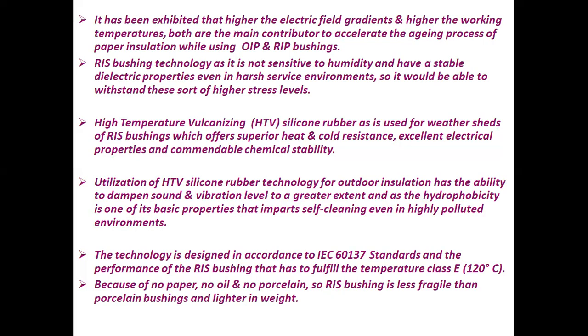High temperature vulcanizing, that is HTV silicone rubber, is used for the weather sheds, that is rain sheds, of resin impregnated synthetic bushings, which offers superior heat and cold resistance, excellent electrical properties, and commendable chemical stability. Utilization of HTV silicone rubber for outdoor insulation has the ability to dampen sound as well as vibration to a greater extent. Hydrophobicity is one of its basic properties, which imparts self-cleaning even in highly polluted environments.